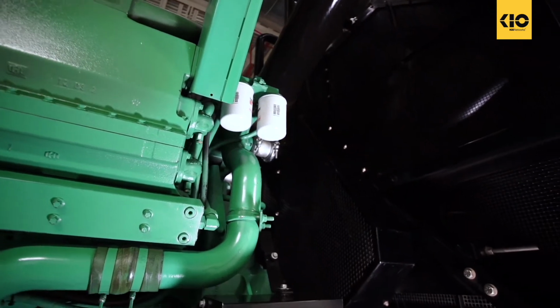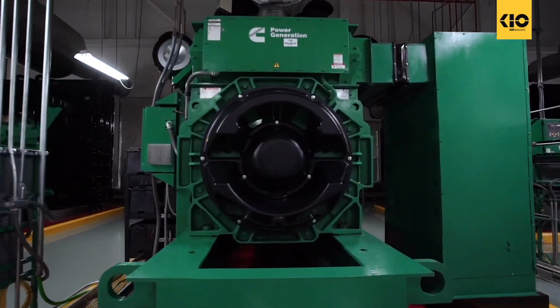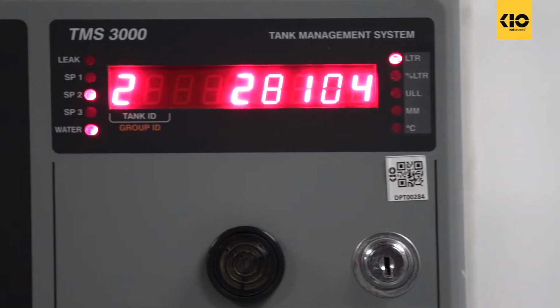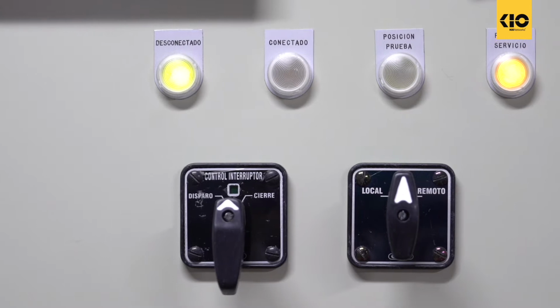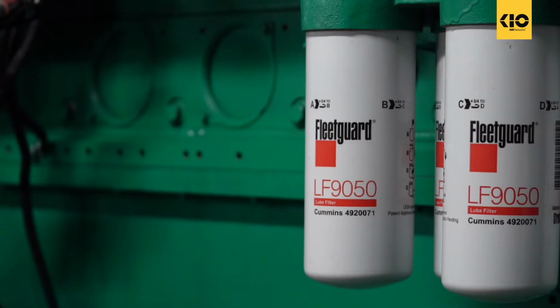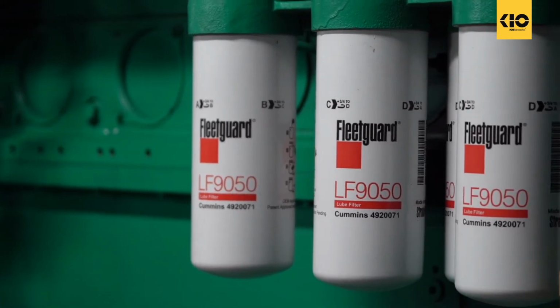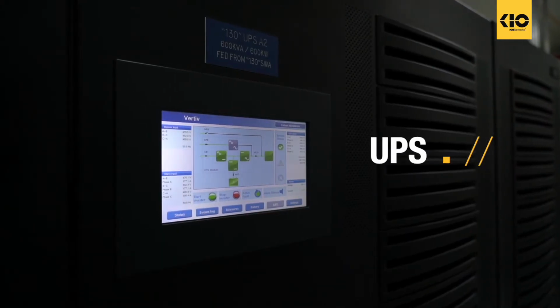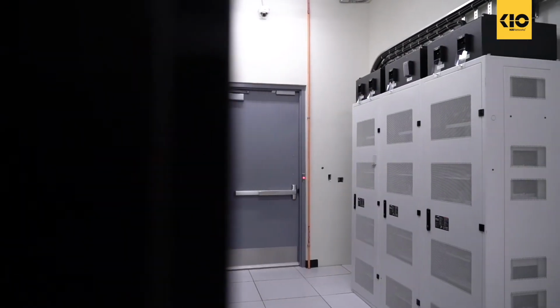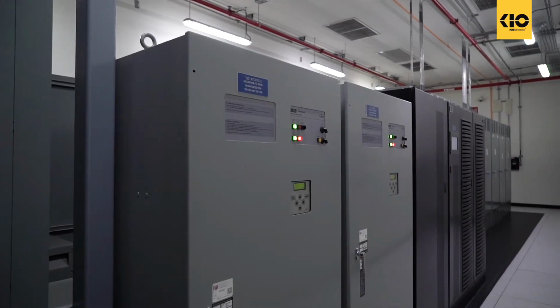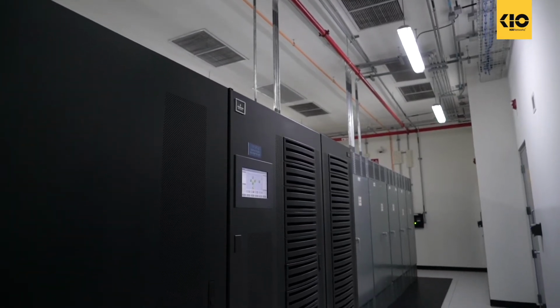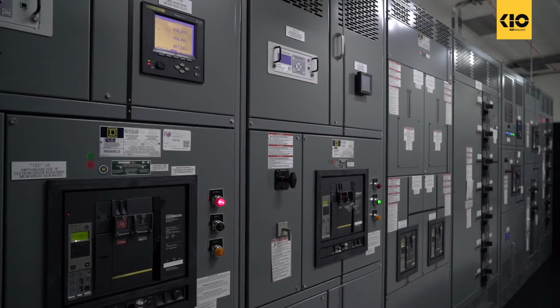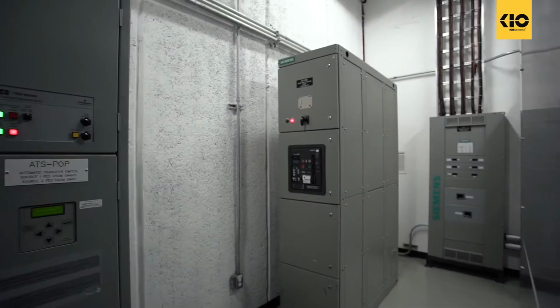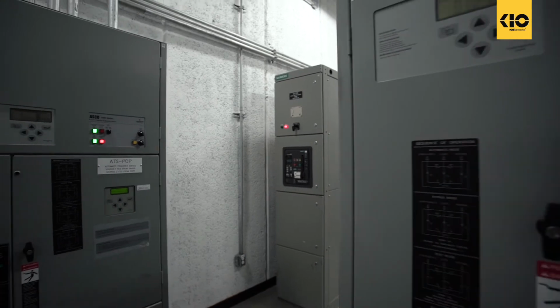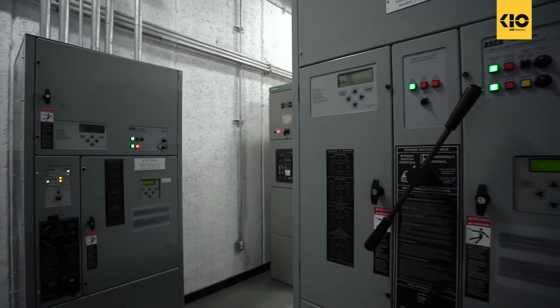It is essential to mention that the maintenance of the generators is carried out by certified personnel, applying the MOP procedures according to the manufacturer's manuals, with functionality tests every 2 weeks and with load banks to ensure their correct operation. The UPS systems and their battery banks provide uninterruptible power to the equipment housed in the data center, while the generators start and reach the frequency and operating parameters. As the external utility power network normalizes, the transfer system performs an automatic sequence to return to the preferred source.